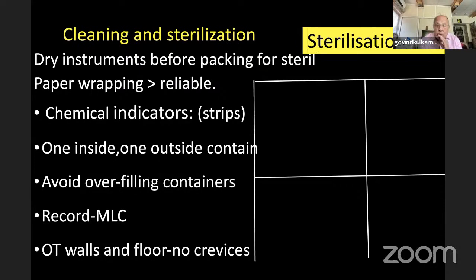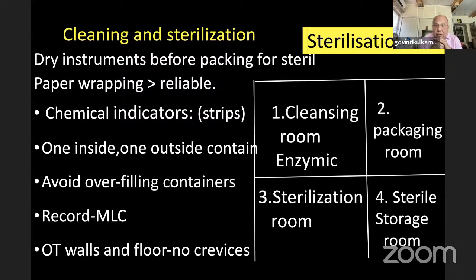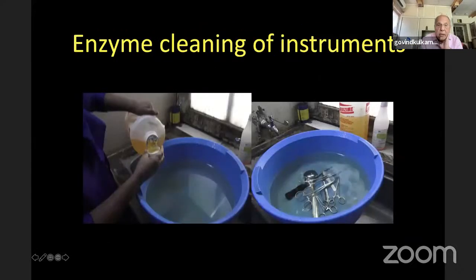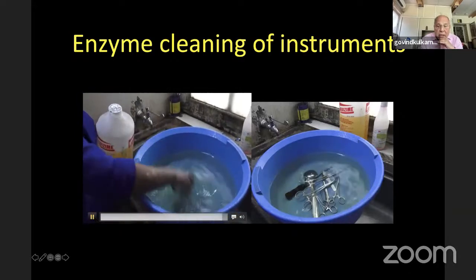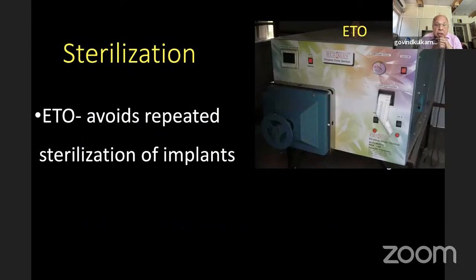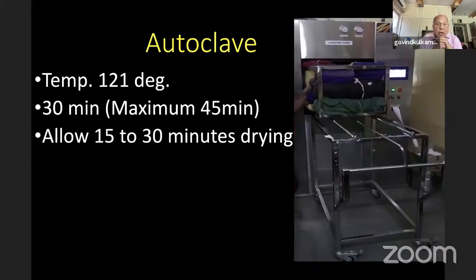Now, the sterilization zone should have a cleaning room, enzymatic. The packaging room should be there, and a sterilization room and a sterile storage room. These all 4 should be separate. Enzyme cleaning of instruments should be done: use the enzyme and then clean it. ETO avoids repeated sterilization of implants. For the autoclave, the temperature should be 121 degrees, with 30 minutes or a maximum of 45 minutes. Allow 15 to 30 minutes of drying.